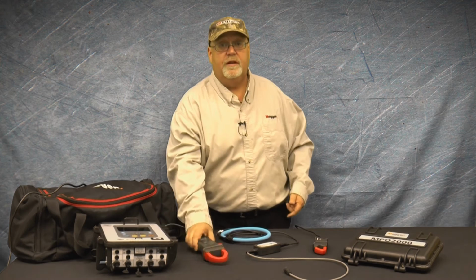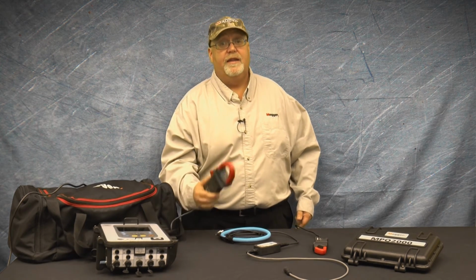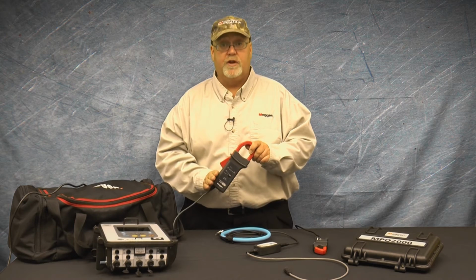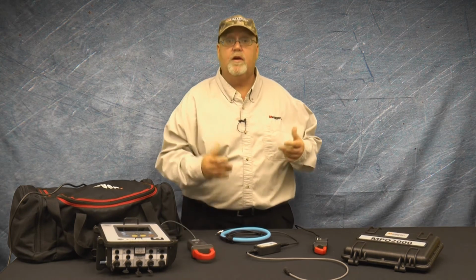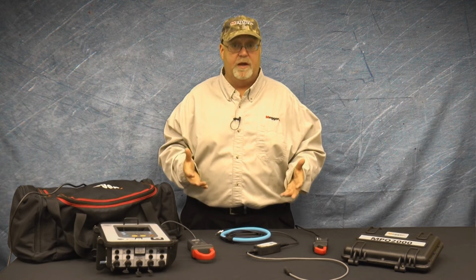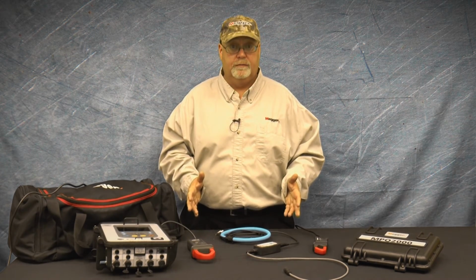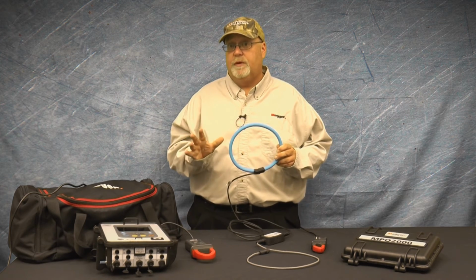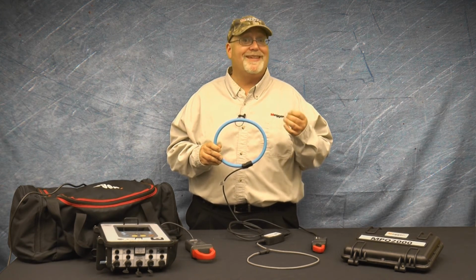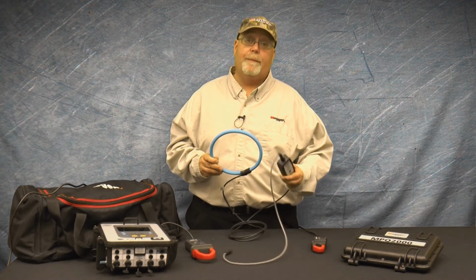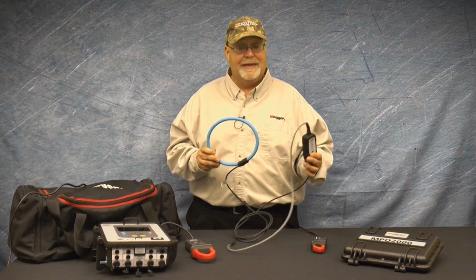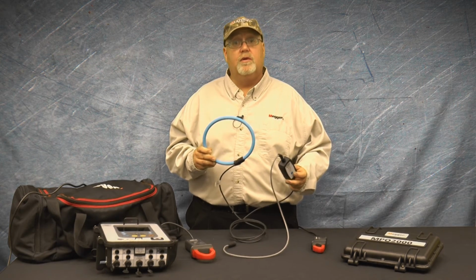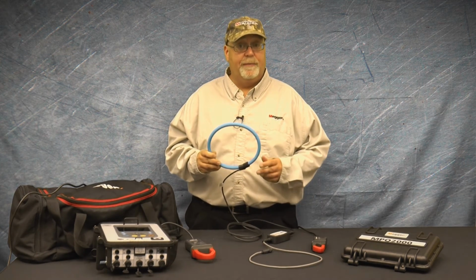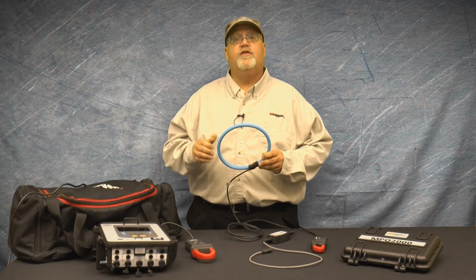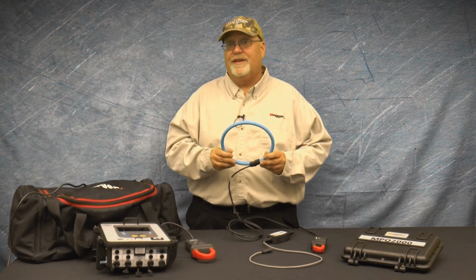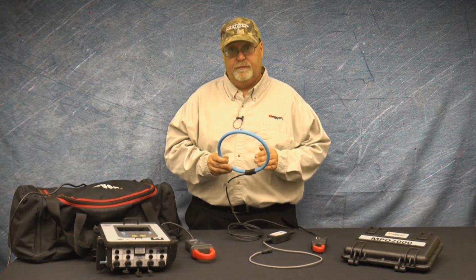If you're measuring DC, you need to use a Hall-effect sensor. And in that case, you have to ask yourself, do I have fresh batteries in it? If your CT requires batteries, you always want to make sure they have fresh batteries before you start the recording. Step 4, what's the approximate range of current you're going to be measuring throughout your test? You want to select the proper range on your CT to match this. If you select a range that's too low, you run the risk of saturating the core or clipping the signal. If you select a range that's too high, you may have increased inaccuracies on the low level of current.